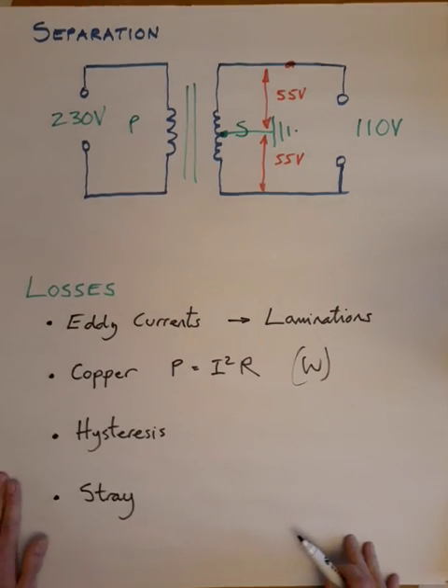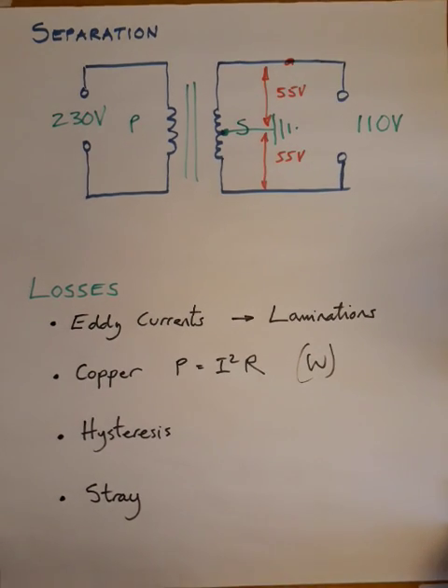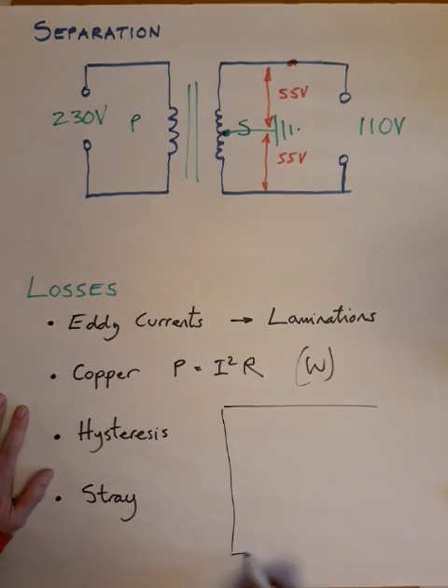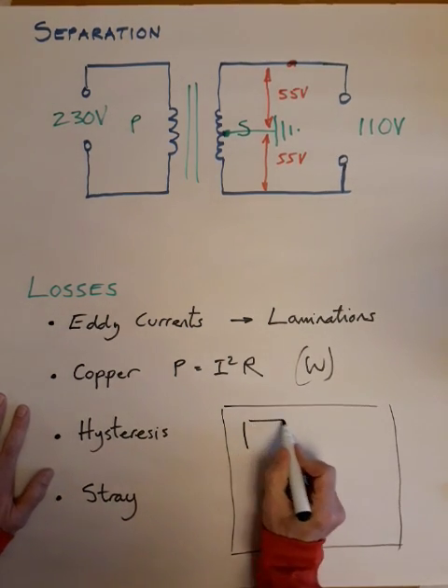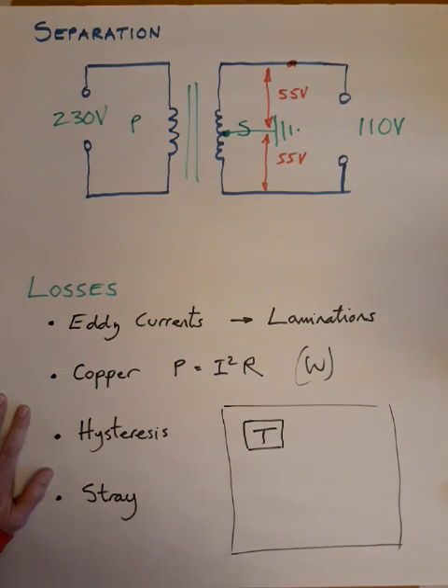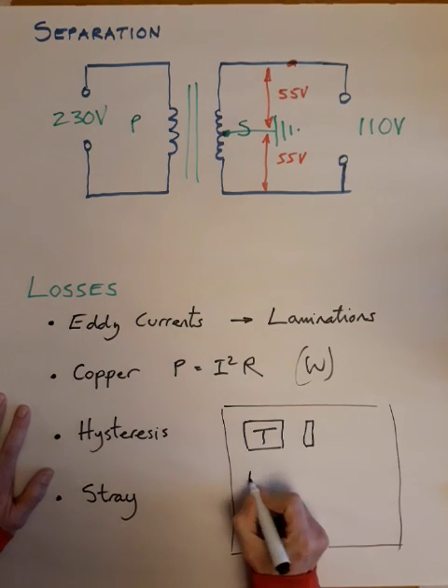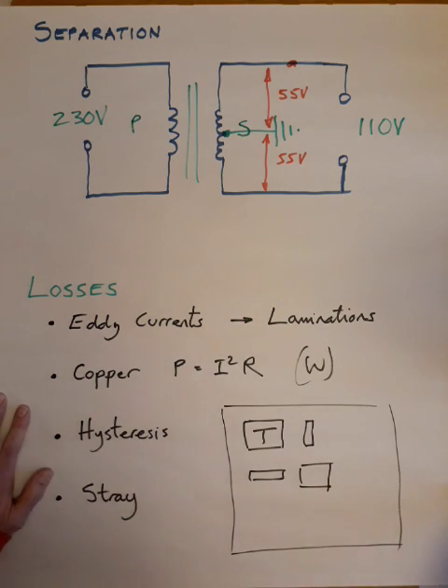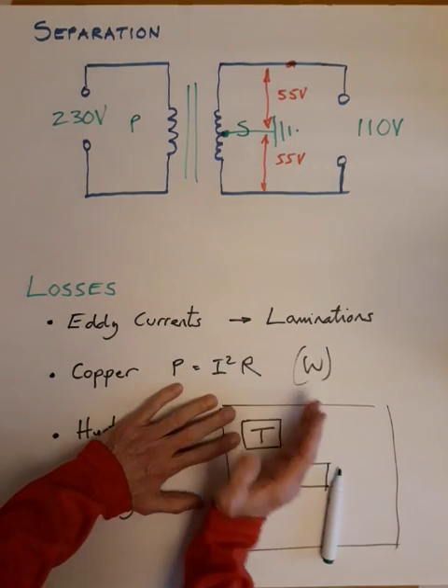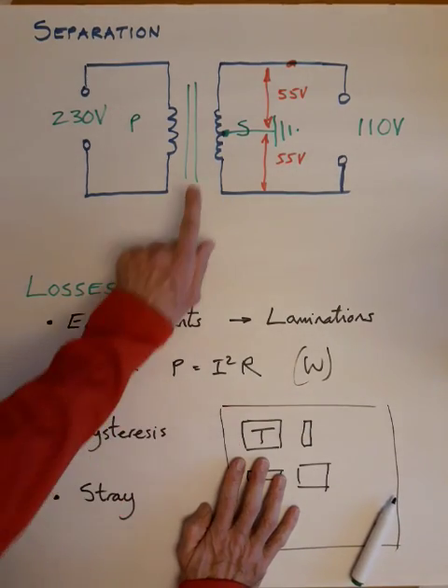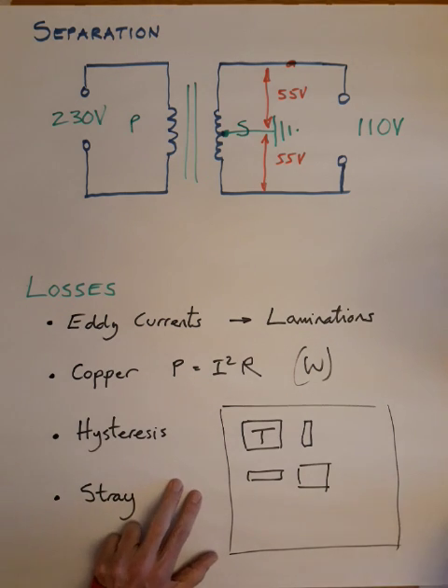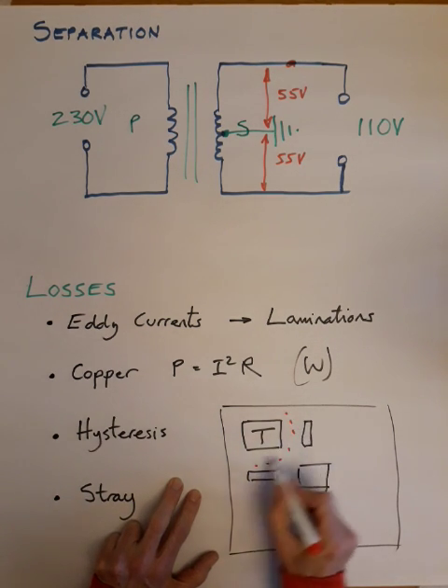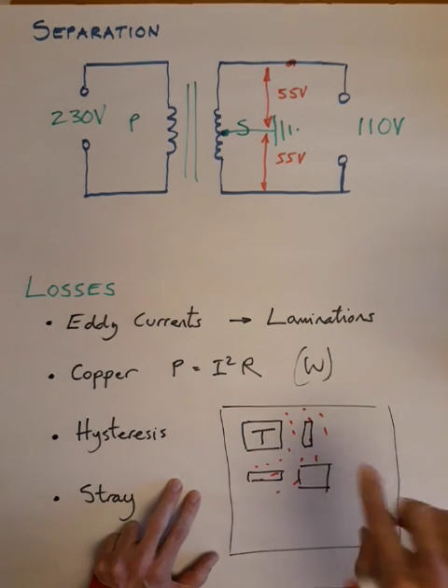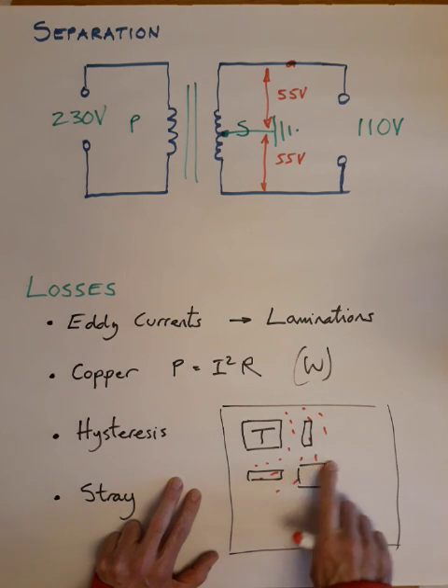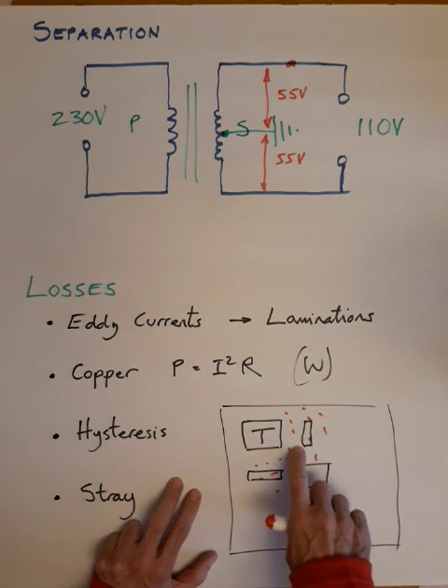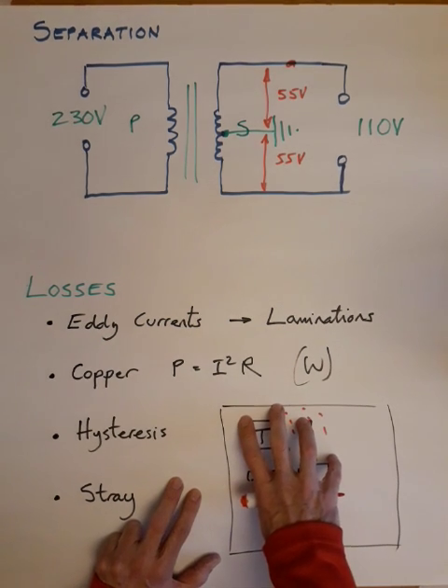Stray losses are a little more complicated and unusual if you encounter them. Imagine a printed circuit board, looking down in plan, with a transformer over here, and other metal components mounted near it. The transformer is radiating magnetic fields in and out at 50 Hertz, just as I described earlier. Components near the transformer may be affected by the magnetic flux, having an EMF induced into them, causing a tiny unwanted current to flow. We're paying for that one way or the other, so it is a loss. That is stray losses.